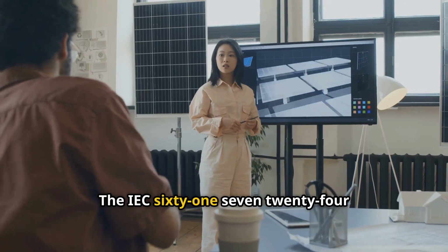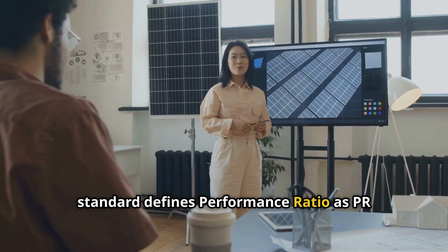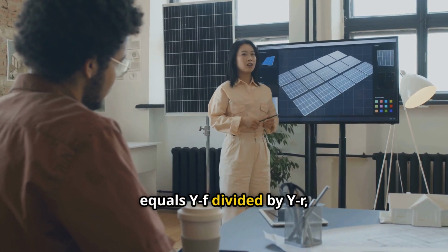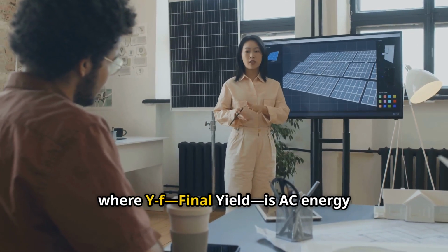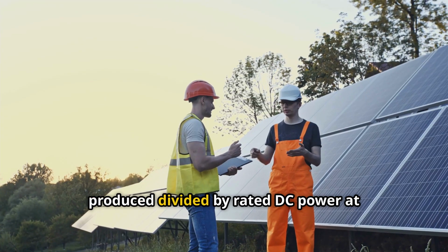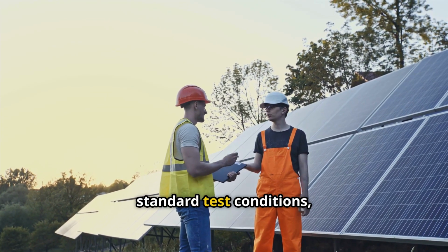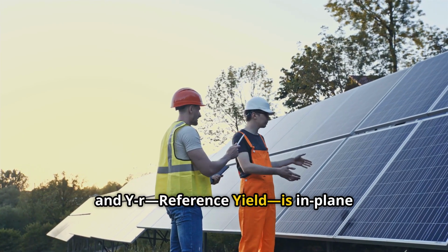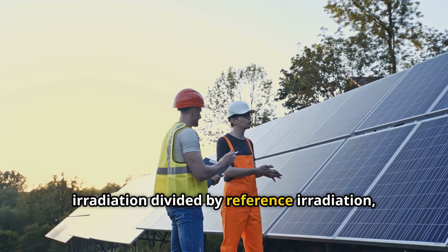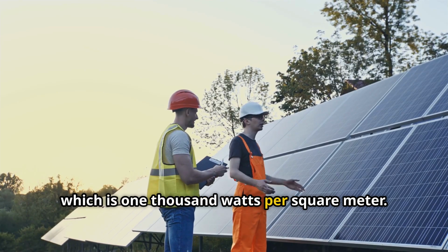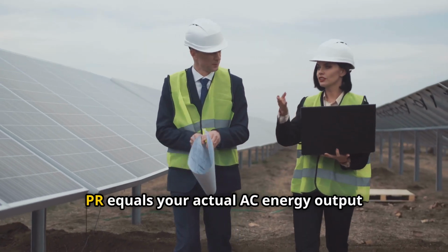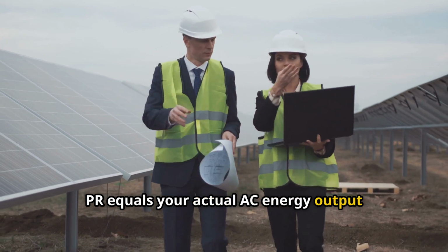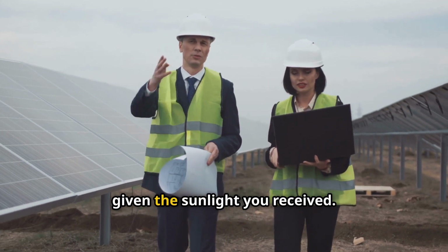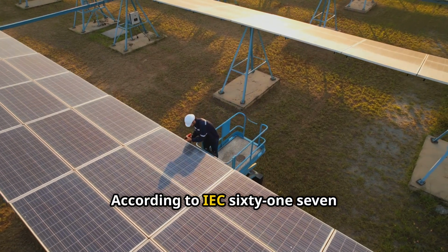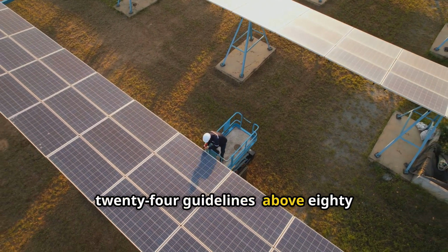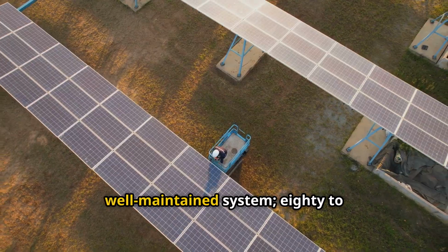The IEC 61724 standard defines performance ratio as PR equals YF divided by YR, where YF, final yield, is AC energy produced divided by rated DC power at standard test conditions. And YR, reference yield, is in-plane irradiation divided by reference irradiation, which is 1000 watts per square meter. In practical terms, PR equals your actual AC energy output divided by what you should have produced given the sunlight you received. According to IEC 61724 guidelines, above 80% means an efficient, well-maintained system.